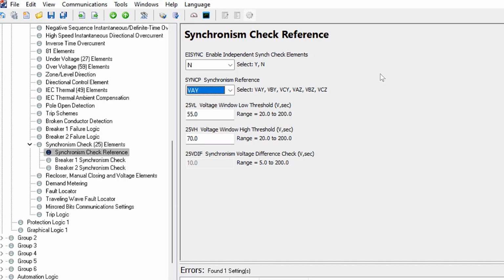So I'm going to leave that at VAY, and then these are the thresholds that I was talking about. The voltage window low threshold, we said that that's 0.9 of the nominal voltage. In our case, that's 59.8. The voltage window high threshold is going to be 73.0 for our case. That's 10% above the nominal voltage.